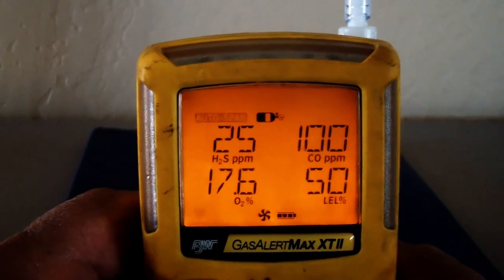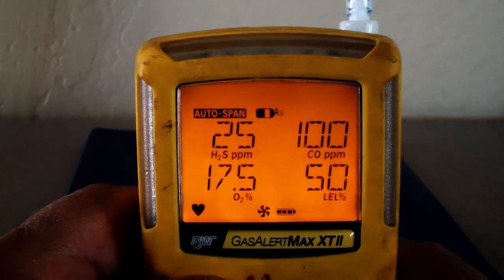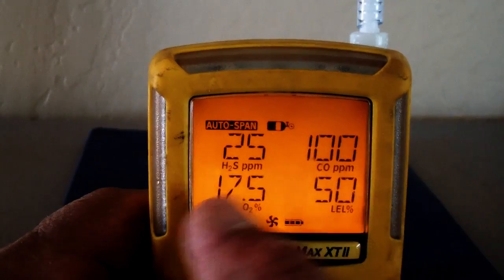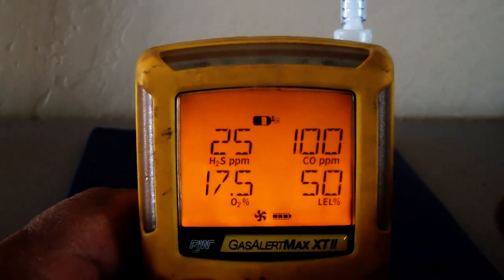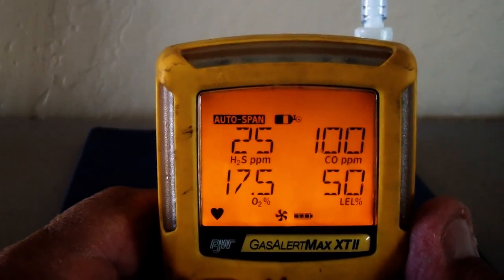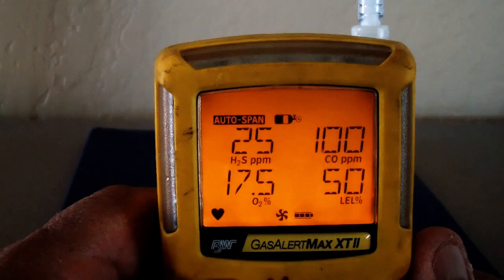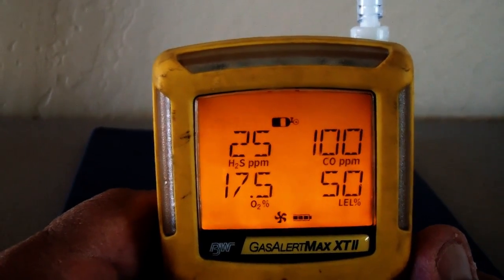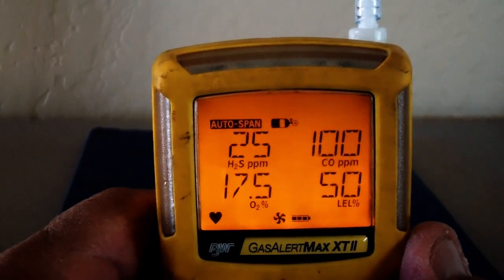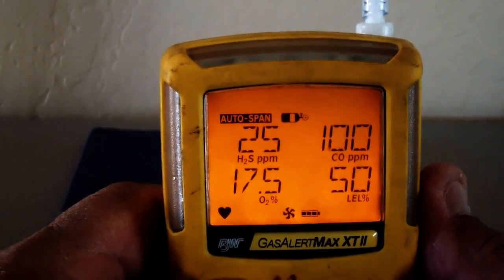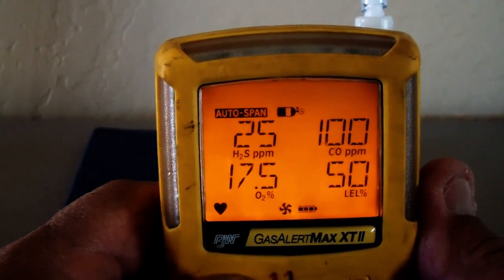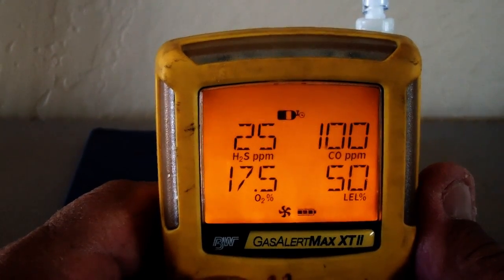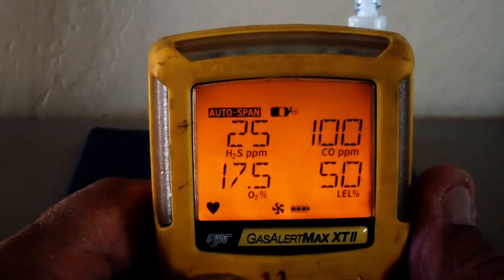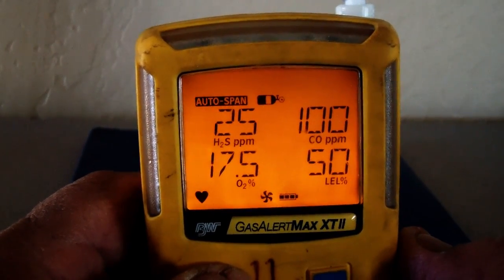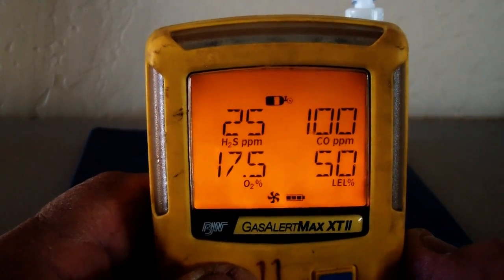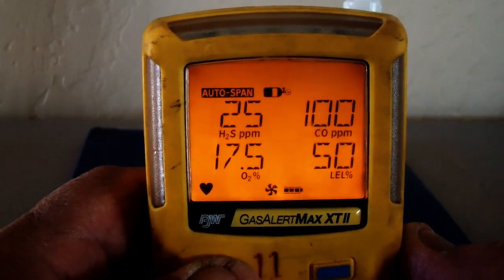Typically, if we have a sensor malfunction or a sensor that's going south on us, during the calibration phase you won't get to the values that you see on the screen. They'll be off. Typically, it's that O2 sensor that will shut down, or the LEL sensor. Both of those are like candles. They're always burning, right? They're burning the air that goes through them to get the reading. So the toxic sensors, the H2S and CO, are pretty stable and they last for several years. Whereas the O2 and LEL sensors, I've changed them out as often as once a year. So you just got to keep an eye on those things.